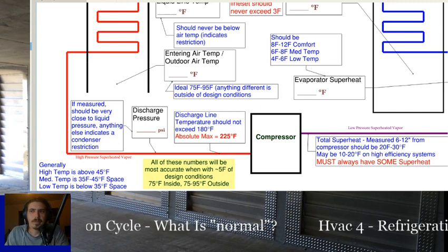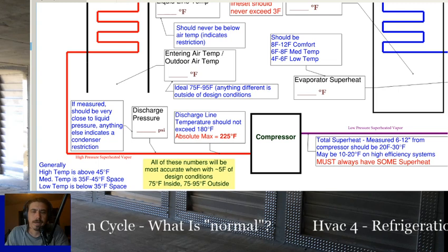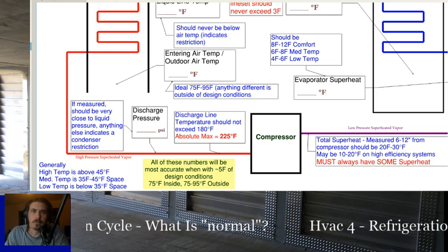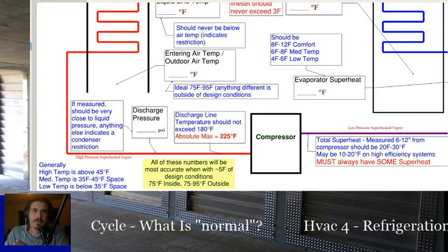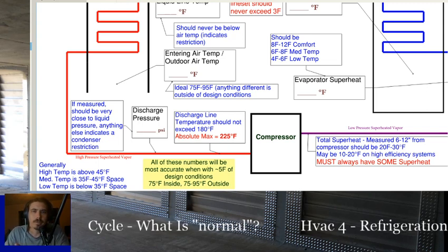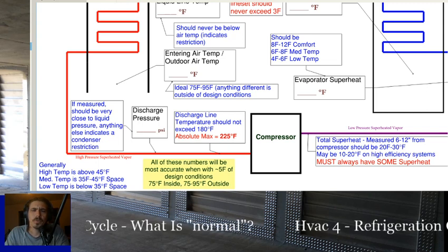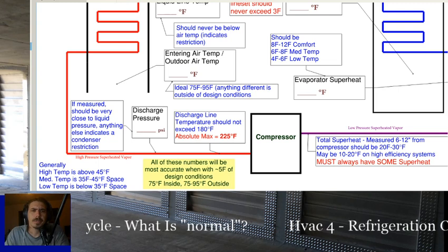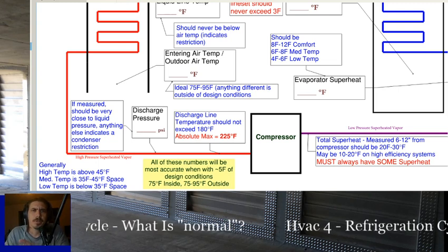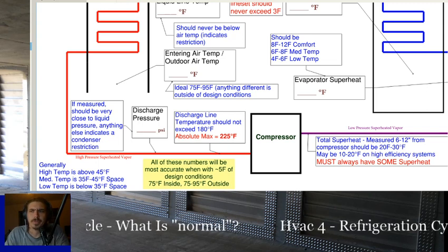The other thing, though, that's more important is when we're talking about pressures, I honestly don't care what the pressure is in the system. The reason is you have different refrigerants you're working with on any given day. And when the switch was made from R22 to R410A, a lot of people said, well, these are higher pressures and your pressures aren't going to look the same and it's going to be different. So you have to get used to what that is.